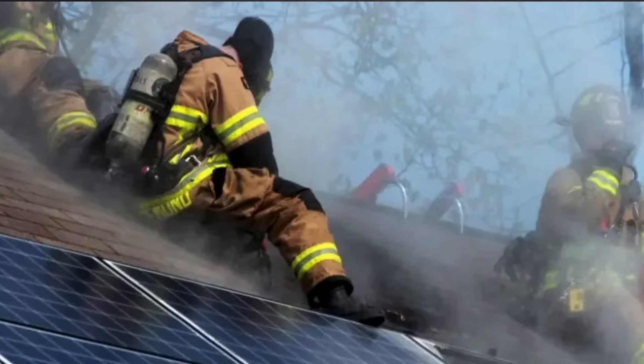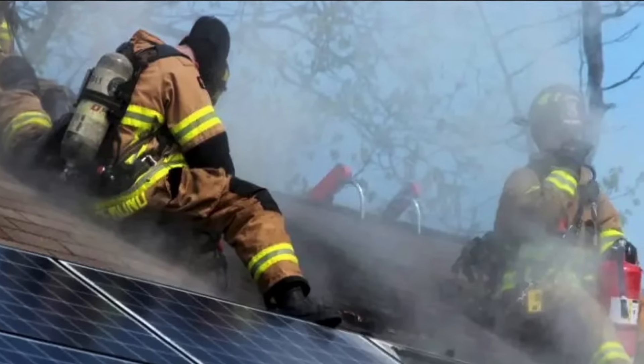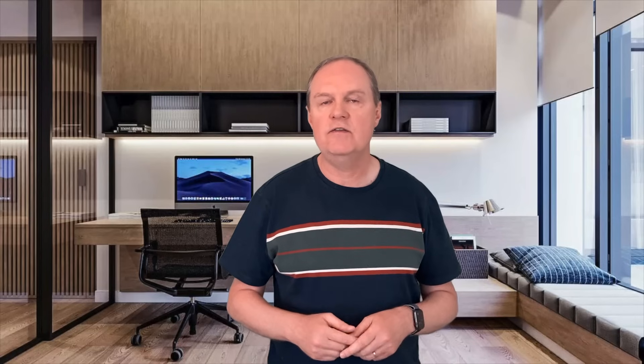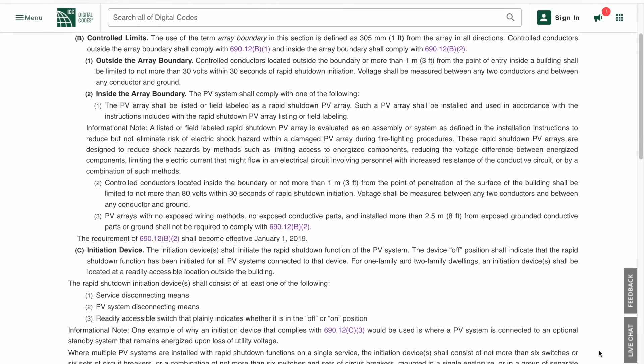Another important benefit of optimizers is all to do with safety. Rapid shutdown is a critical safety procedure of solar panel installations, required to ensure the safety of emergency responders and electrical workers during maintenance and repair activities. During a fast shutdown procedure, the electrical output of the solar panels is rapidly reduced to a safe level. This is especially important in high-voltage systems where the potential for serious injury or death is significant. String inverters can certainly shut off to prevent the energy generated by the modules from getting past the inverter, but the panels will continue to generate electricity when the sun is shining, creating voltage and current on the cables between the panels and the inverter. As a result, most rapid shutdown regulations today require shutdown to occur at the panel level — hence the use of module-level power electronics such as optimizers or microinverters.